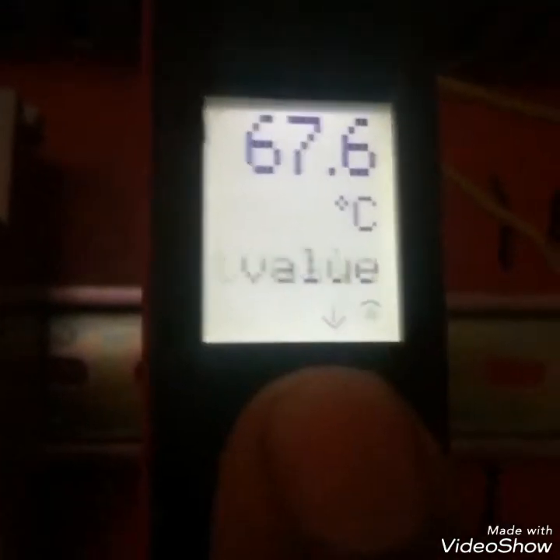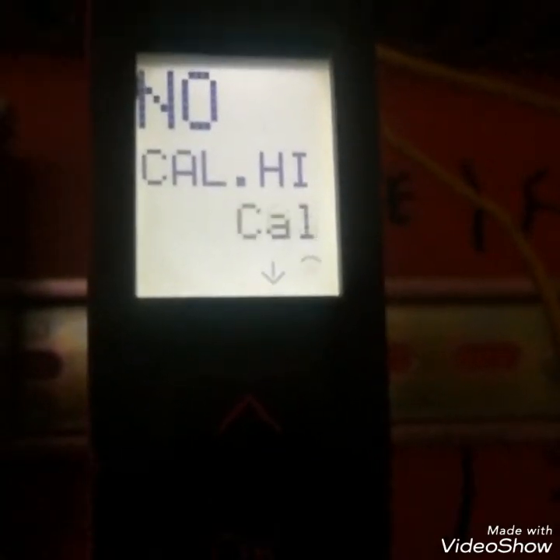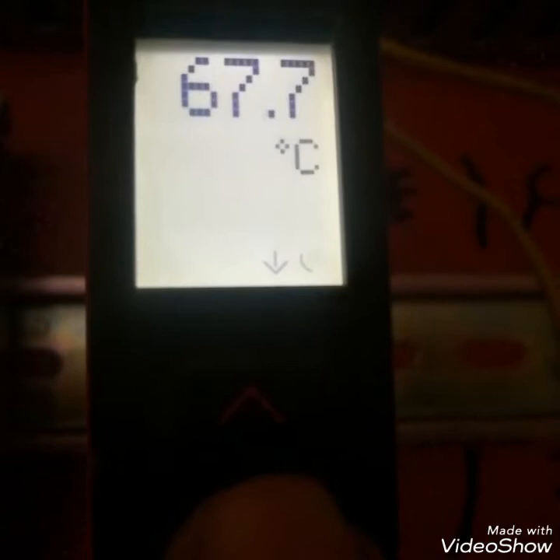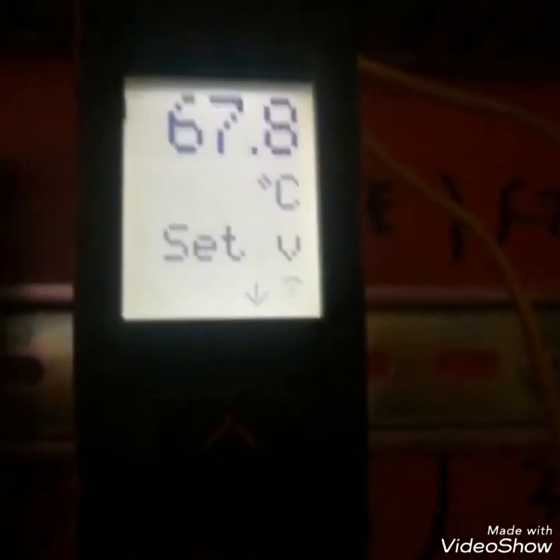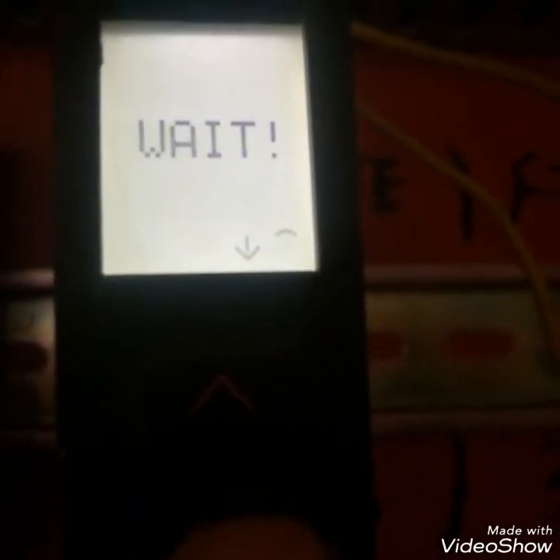In calibration setup, calibration low means zero calibration. Yes, we are doing zero calibration. We can adjust zero manually as per our requirement while giving the 0 temperature. High calibration, yes, here we can adjust span calibration while giving the specific temperature of high range. We can use calibration, or we can say that we don't want to use it. Here I am not using it because I am not calibrating. I am just showing you the parameters.